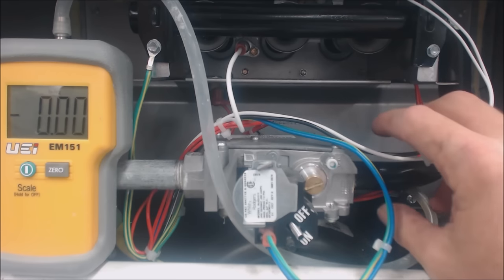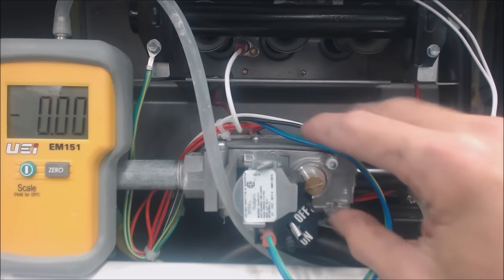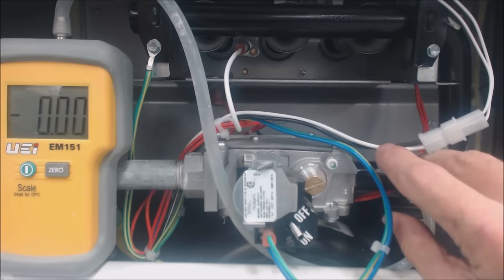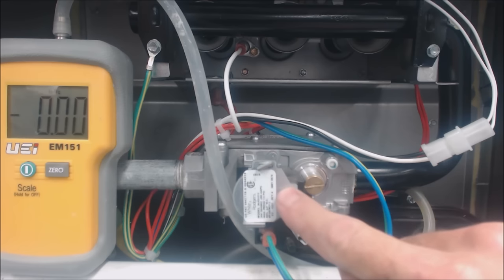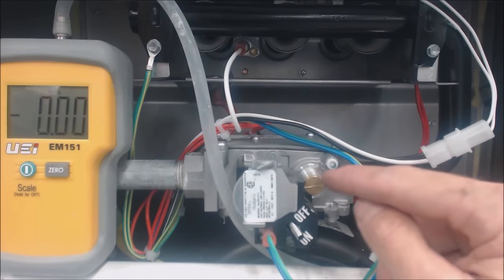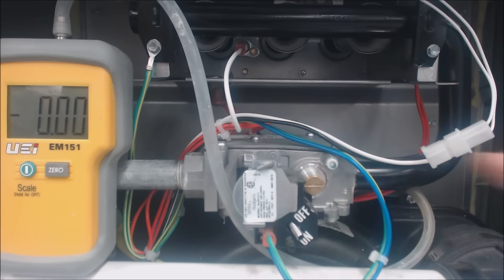If you see an additional brass screw on the unit over here on the gas valve — two here and then a third one there — that would be a two-stage gas valve. If you do not see a brass screw on the electrical gas valve, that may be a variable speed gas valve. In this case it's a single speed gas valve, denoted by the single nut, and on the rating plate there was only one pressure. If it was a two-speed unit, it would have two pressures in inch water column.